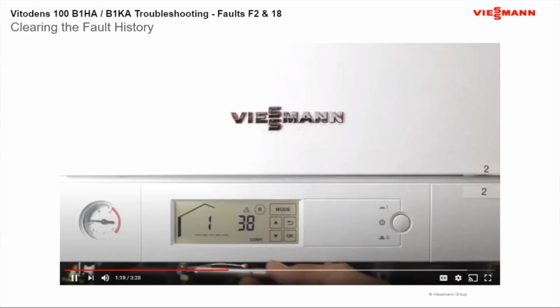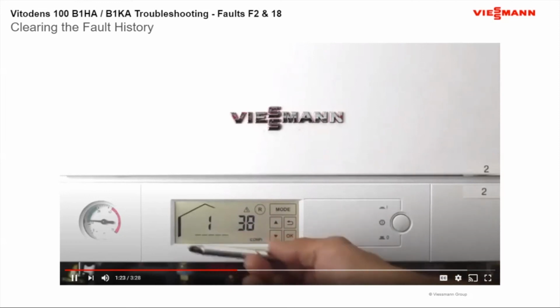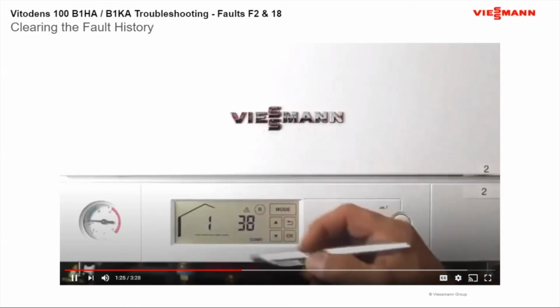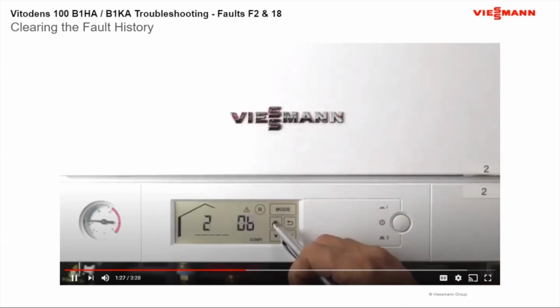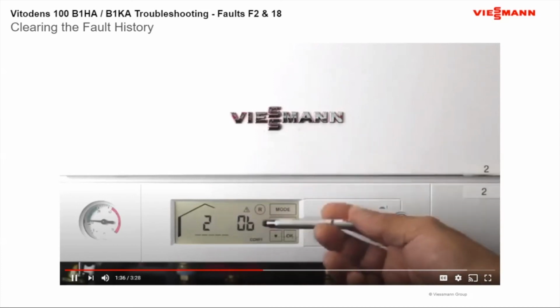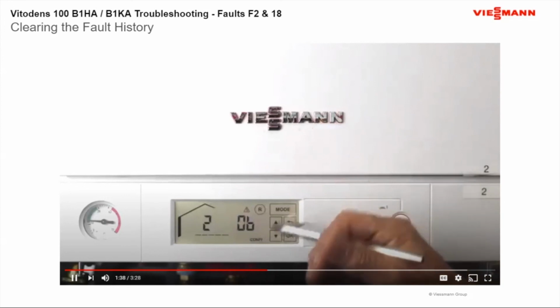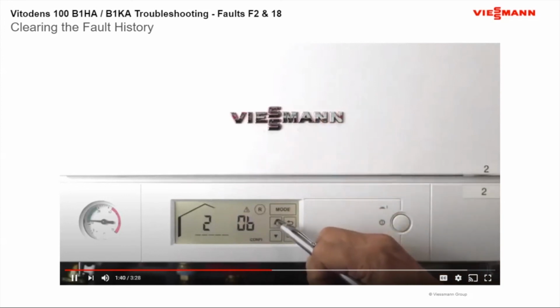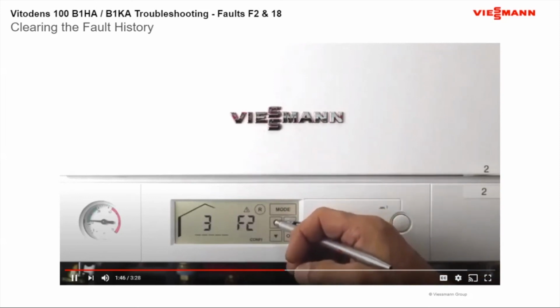As you can see, in our fault history, fault number 1, the newest fault, is a 38. If we go up with our up arrow, we can see that we've had an OB fault. A lot of these faults we do have videos that you can watch to see how to fix. And these could have been prior faults that nobody cleared before they left. Our last one here is an F2 fault, and that seems to be all the faults we have on this boiler.